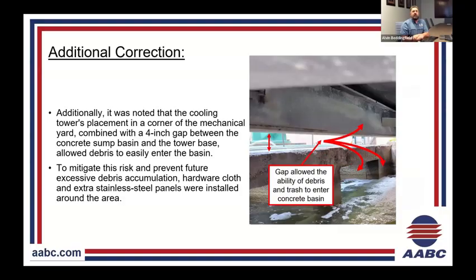Additionally, one thing we pointed out to the mechanical contractor and the EOR was that this cooling tower is in the corner of the mechanical yard, right by the garbage dumpsters for the K through 12 campus. There was a good gap, in some points almost 6 inches, around the basin. Our concern was that trash would collect in that corner of the mechanical yard from wind, or from the cooling tower pulling it in, and that gap would allow debris to enter the concrete basin and collect.